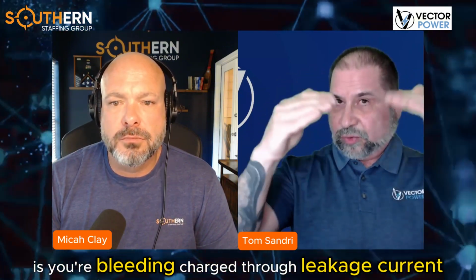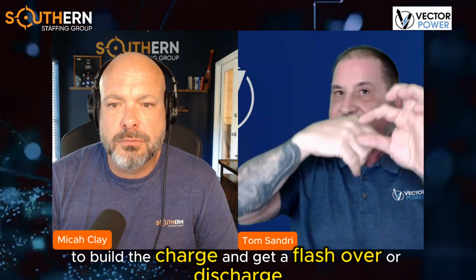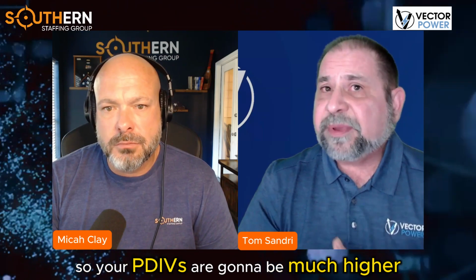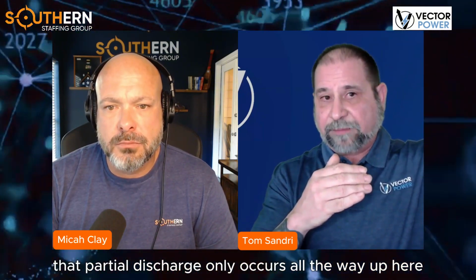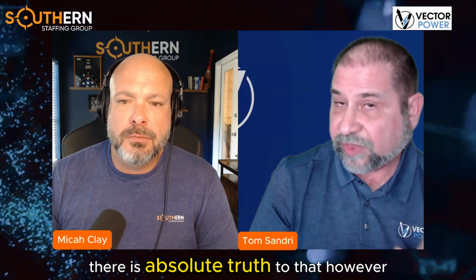So what's happening is you're bleeding charge through leakage current. It's going to force you to go higher in overall magnitude to build the charge and get a flashover or discharge. So your PDIVs are going to be much higher than in the real world, giving you a false sense of security that partial discharge only occurs all the way up here, when in reality it might be occurring here. There is truth to that. There is absolute truth to that.